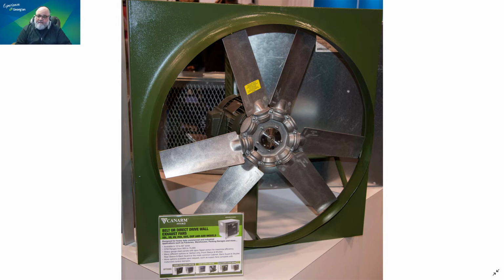The amount of energy being used is directly proportional to the amount of air being moved as a rate, whether per minute or per hour. So the horsepower of the motor is supposed to correspond to the power needed to do that work, moving that air at that rate.